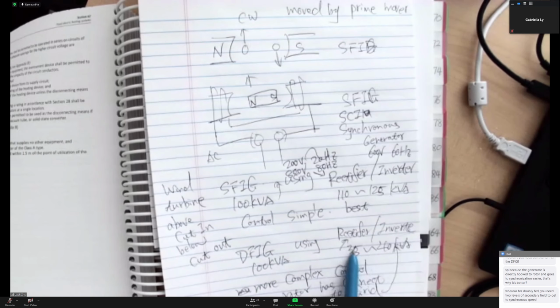Yeah, for double feed, you have to feed different frequency into the rotor, and at the same time, you have to monitor the speed, because at different wind speeds, you need to feed a different frequency in there. If the speed is higher, you need to feed the opposite direction AC in there. But if the speed is lower, you need to feed the positive direction AC into the rotor. That's why it's much more complex controls. Whereas with the first one, you don't really care, as long as the rotor is moving, you will generate something.